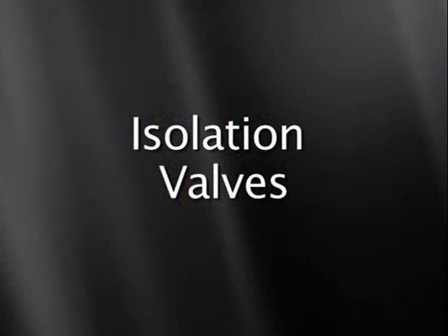Inlet and outlet gauges allow visual monitoring and troubleshooting for pump performance. These are typically liquid-filled and may include isolation valves. Ball valves are typically provided at the inlet and outlet of each pump to provide isolation for maintenance. An internal relief valve is provided to assure that the pump pressure will not exceed the motor capability, and also to provide gross pressure regulation for the pump discharge.